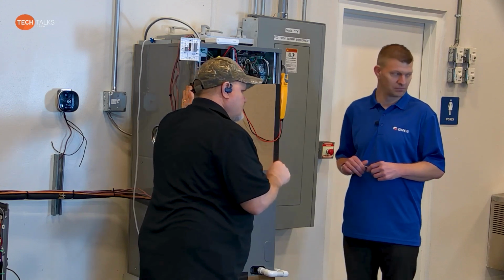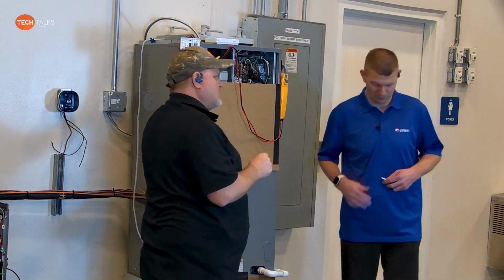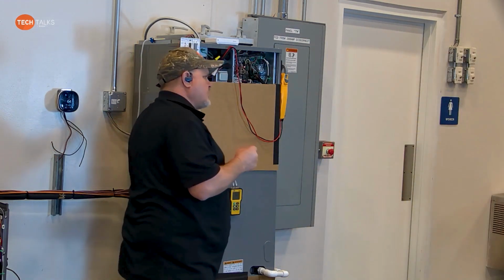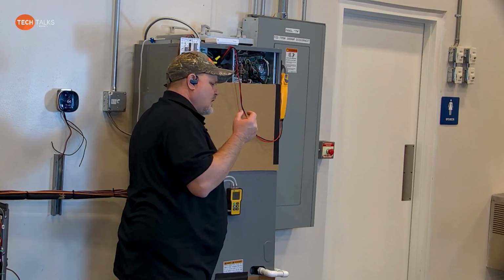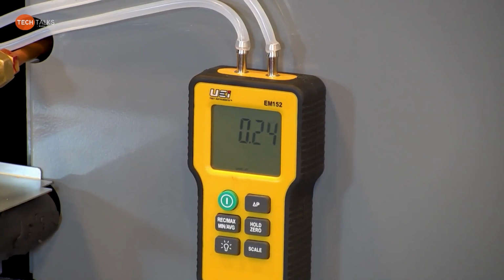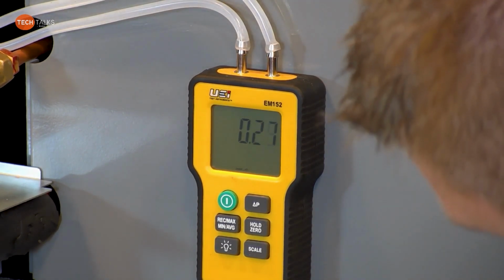Even though the reversing valve is energized, and it's energized off of the thermostat OB terminal, you set that up to energize the reversing valve in heating mode, okay? So it stays energized the whole entire time that the thermostat's set to heat, okay? But that's the 24 volt signal, okay?